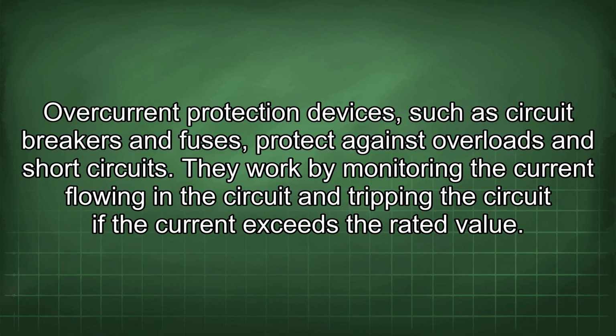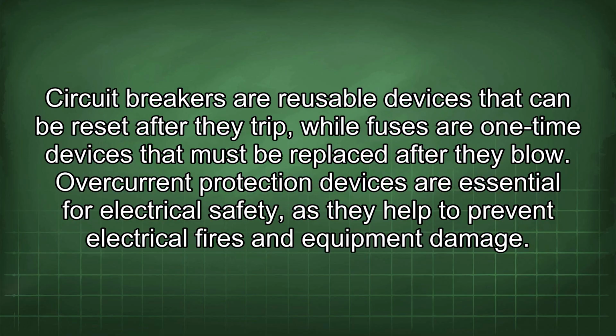Overcurrent protection devices, such as circuit breakers and fuses, protect against overloads and short circuits. They work by monitoring the current flowing in the circuit and tripping the circuit if the current exceeds the rated value. Circuit breakers are reusable devices that can be reset after they trip, while fuses are one-time devices that must be replaced after they blow.